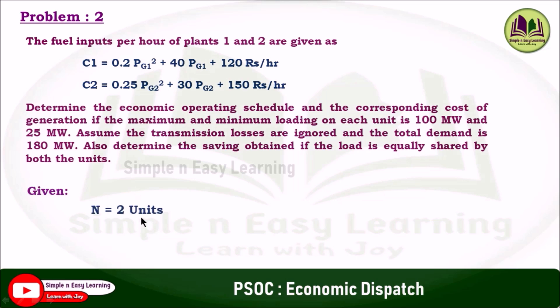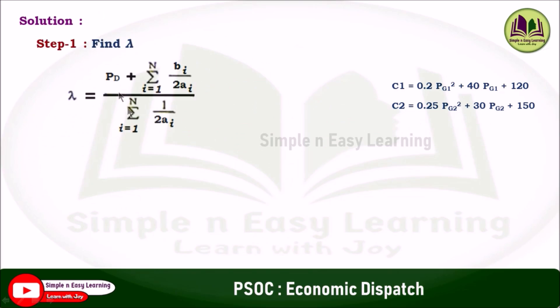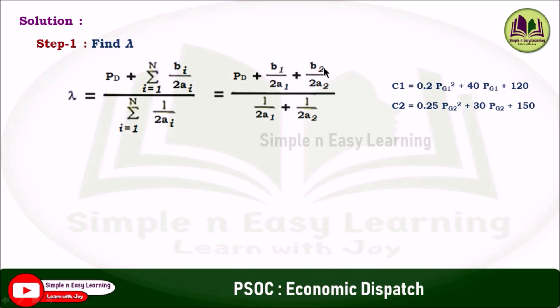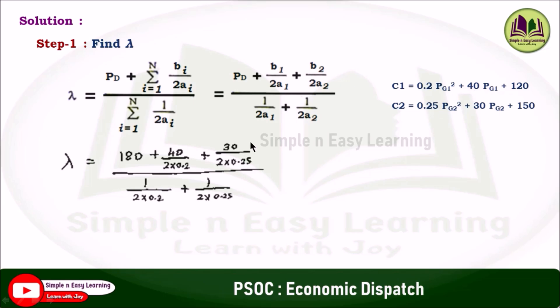Here there are two units, so n equal to 2, and the demand is 180 megawatt, and the limits for both units are 25 to 100 megawatt. Step 1: find lambda using this formula, substituting n equal to 2. The formula is expanded as: PD plus B1 by 2A1 plus B2 by 2A2, divided by 1 by 2A1 plus 1 by 2A2. The coefficient of PG1 square is A1 and coefficient of PG1 is B1. Substituting values — demand is 180, B1 is 40, A1 is 0.2, B2 is 30, A2 is 0.25 — we get lambda equal to 75.556.